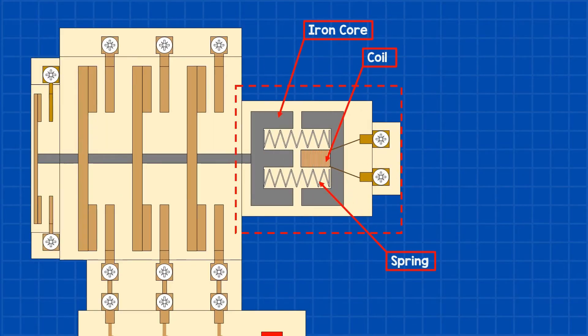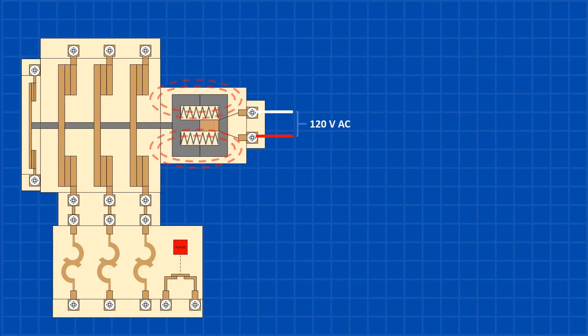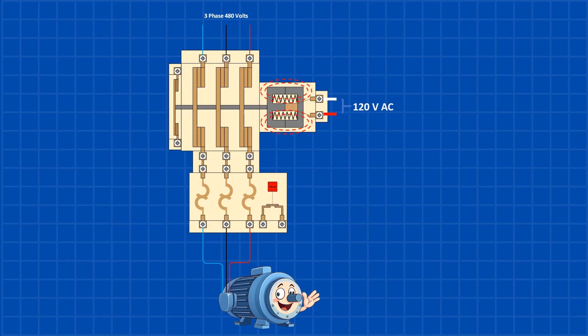The coil typically consists of three main components: an iron core, a main coil, and springs. When the correct voltage, 120 volts AC in this case, is applied to the coil, it creates a magnetic field that draws in the iron core. This movement closes the contacts, enabling power to pass through them and the overload elements, which energizes the motor. The motor continues running until power is removed from the coil.